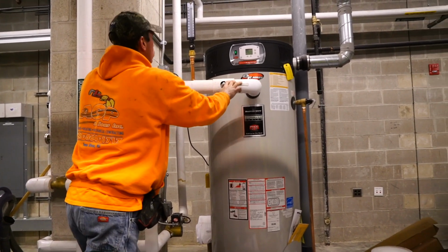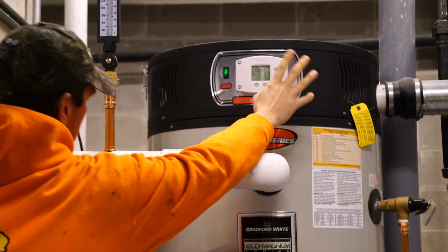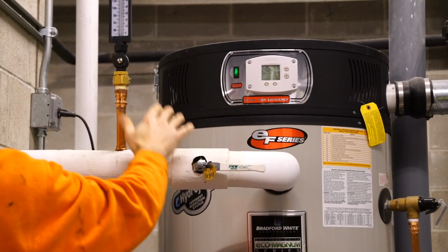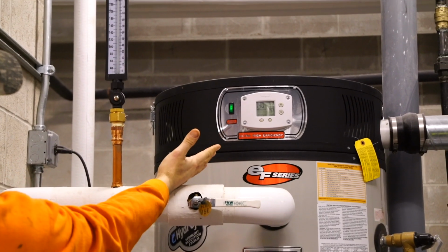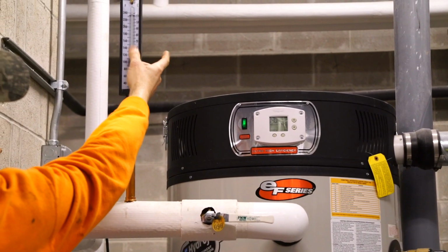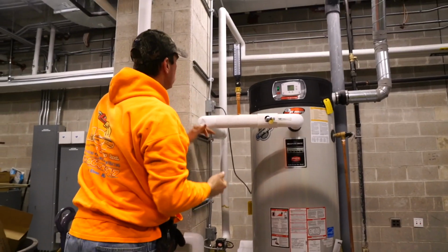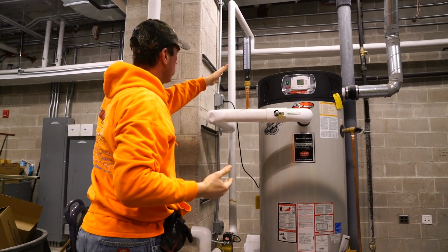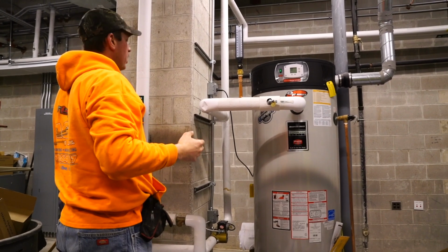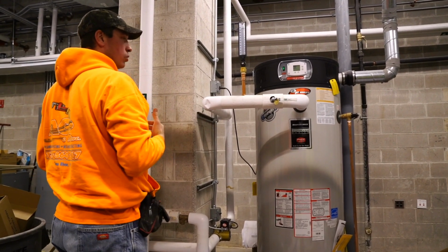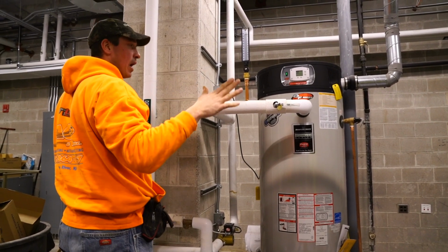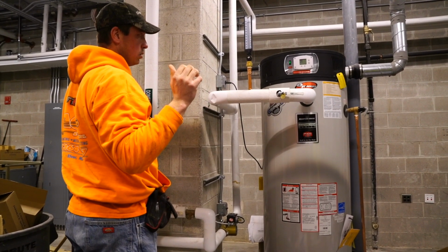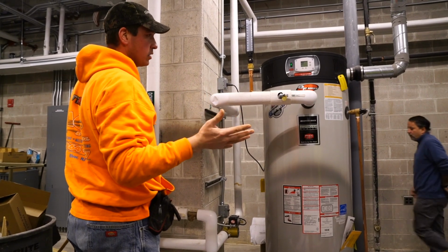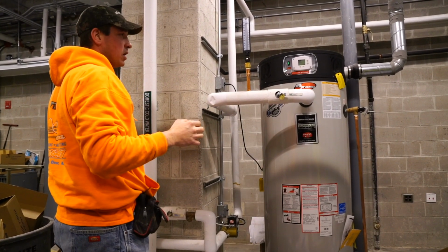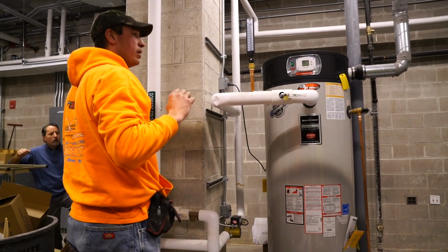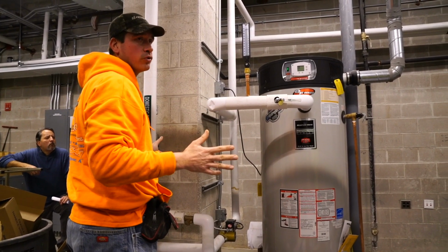I have this set to 140 degrees. You don't need to change it, and I'll show you why in a second. On your hot side coming out, the tank's set to 140. There's no water flow right now, so it's actually reading 130. Once the water flows, it might show higher on the thermostat, up to 140. But on this side of the wall, I have a mixing valve. So all the hot water goes into a mixing valve and then gets distributed out through the building, just because 140 degree water is hot at sinks and stuff like that. So I have the mixing valve set to 110 degrees. So anything going out to sinks anywhere in the building is never over 110 degrees.